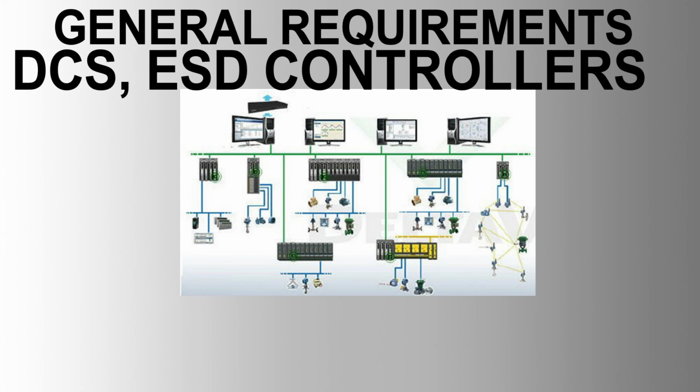8. MCC interface. Communication. ESD controllers should interface with motor control centers, MCC, using standard industrial communication protocols such as Modbus, Profibus, or Ethernet IP. Ensure real-time monitoring and control of motor operations, including start-stop commands, status monitoring, and fault diagnostics. Integration. Integration with MCC should allow for seamless operation and coordination during emergency shutdown scenarios. MCCs should provide feedback to the ESD system on the status and health of motors and associated equipment.